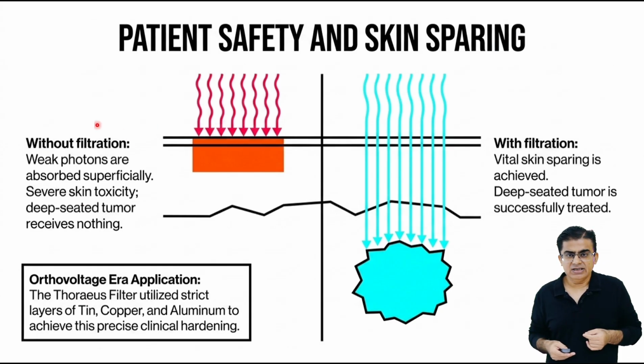If you do not safely filter out the weak low energy photons, they are of absolutely no clinical use. These weak photons simply cannot reach a deep-seated tumor. Instead, they will be completely absorbed in the patient's superficial skin layer. This would unnecessarily increase the surface dose and cause severe skin toxicity.